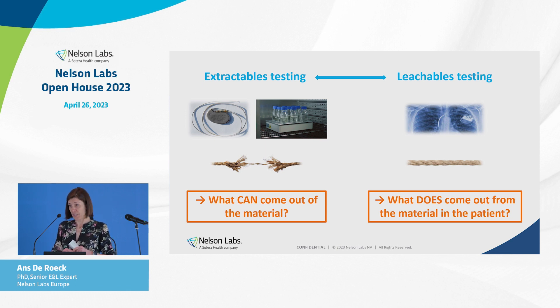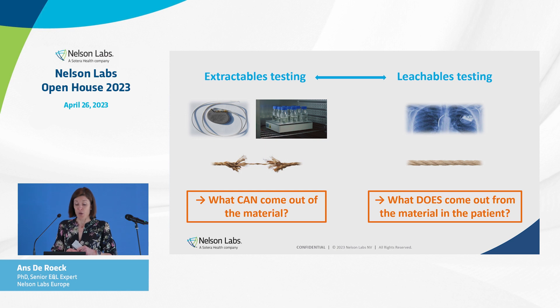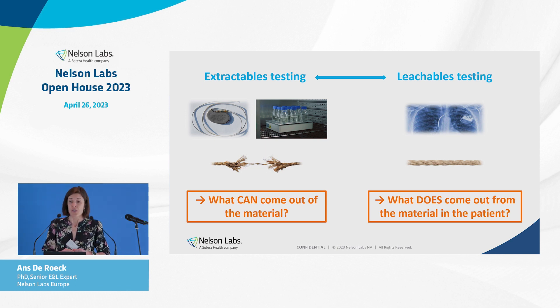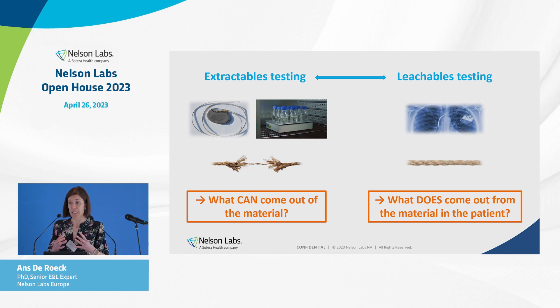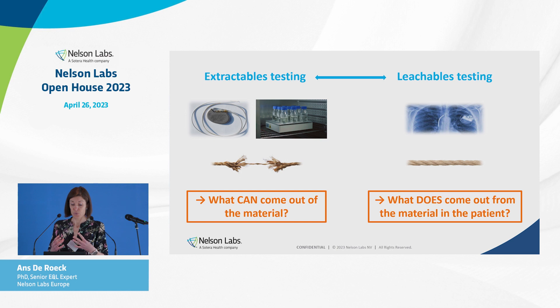You want to know what comes out from the material in the patient, but it's obvious that you cannot test it really inside the patient. So in the case of medical devices, leachables testing is in fact more a simulated-use extractable study, where you simulate as closely as possible the clinical use but in the lab — more simulated-use conditions, less aggressive than those used in extractables testing.